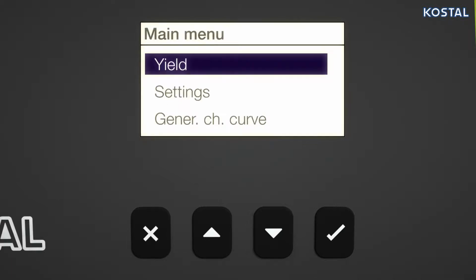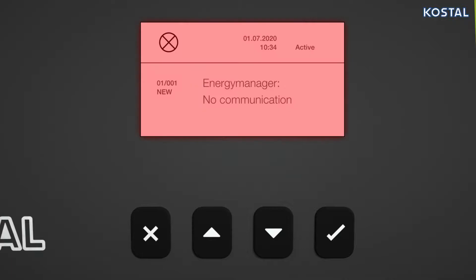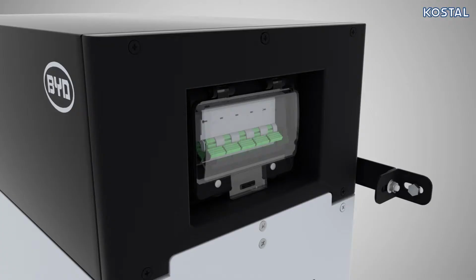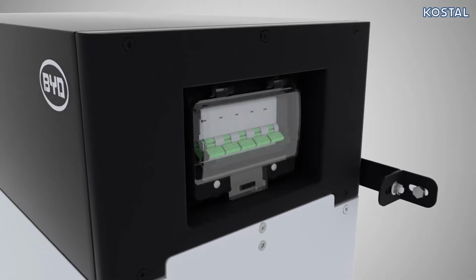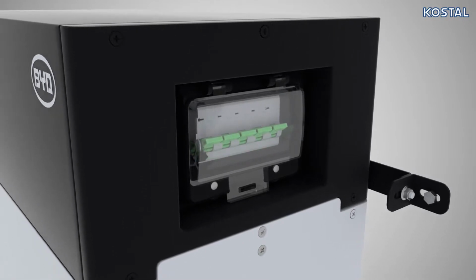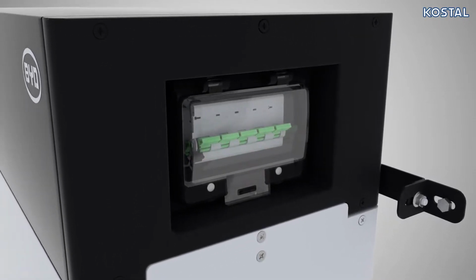Once you have confirmed the configuration, the display shows incorrect communication with the smart energy meter. This makes sense because the battery functionality first has to be configured in the smart energy meter. Now use the fuses on the right-hand side to switch on the battery system. The system starts the initialization process.